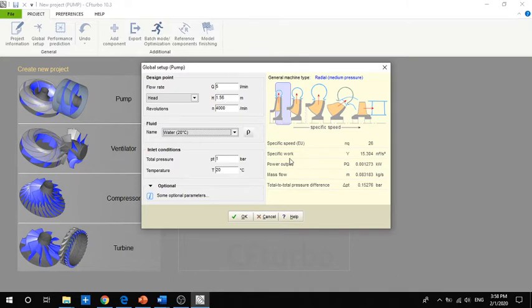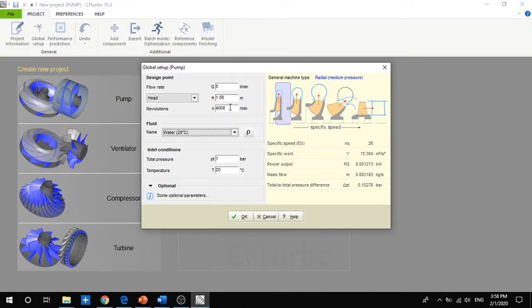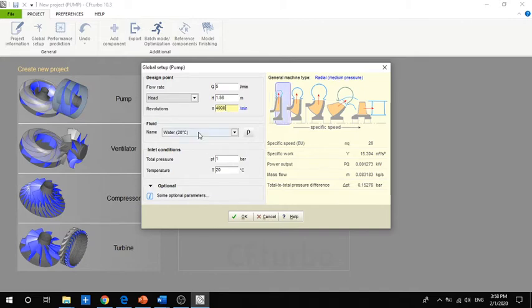We can see directly what these values are affecting. The specific speed is created automatically, and based on the specific speed the program can determine the type of pump — we have radial flow, axial flow, and mixed flow in between. If we change it to 3000 RPM, we can see the pump type changes automatically.